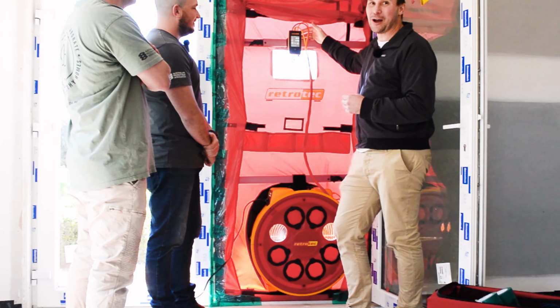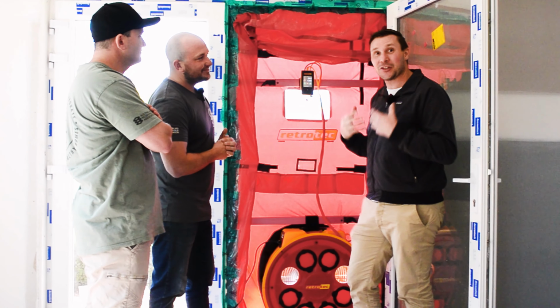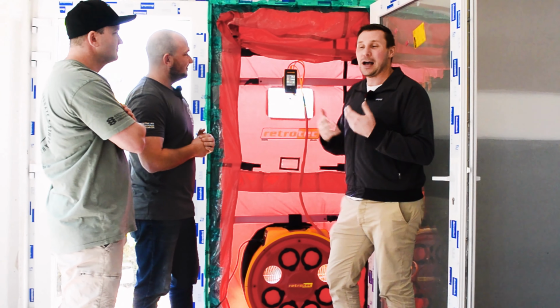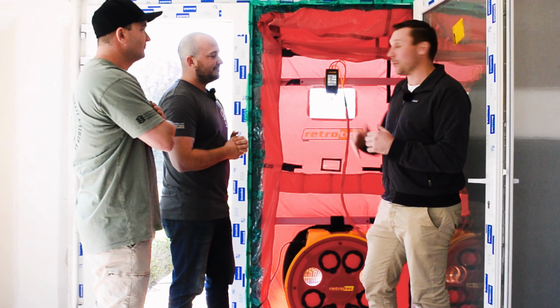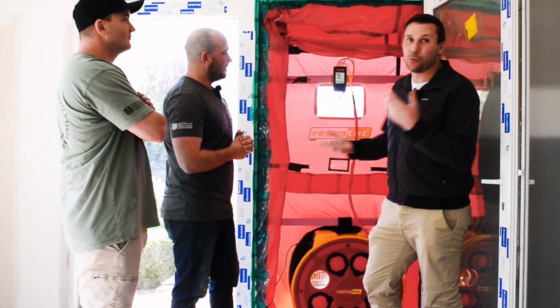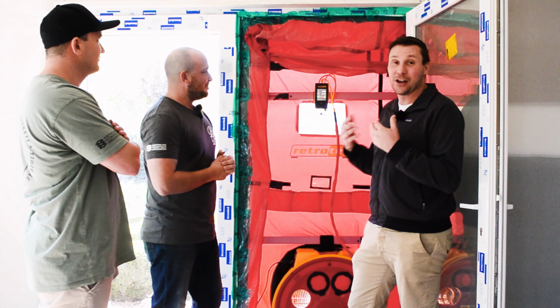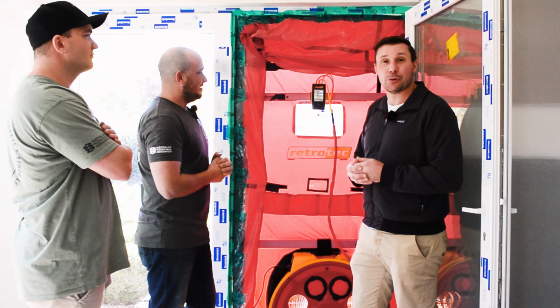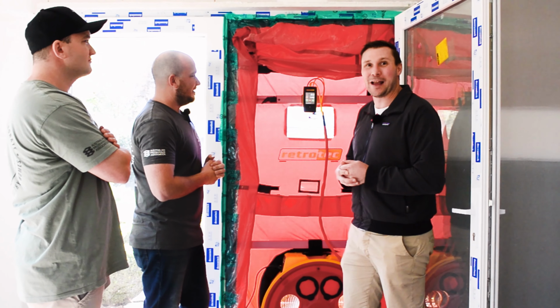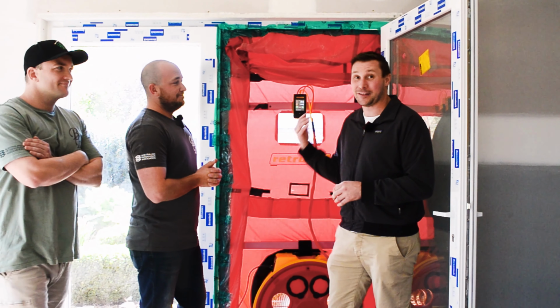All right, so we're already sub 2 air changes an hour. As Dean said, we were at 23. So this is personally the most significant improvement that I've had in a project for an existing house. From 23 to, we're getting close to 1.5 air changes an hour now. So we're almost at the EnerPHit 1 air change an hour requirement. I dare say, with a little bit more detailing on some of the leakage that we'll find as we walk around the home, we'll probably have this sitting around 1 air change an hour. So that's a phenomenal result. Well done, back with the team.